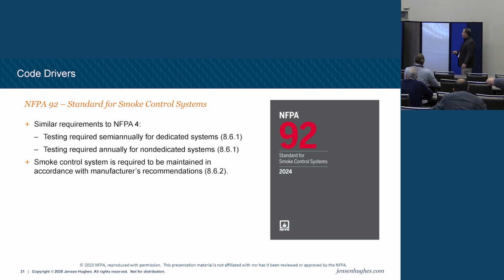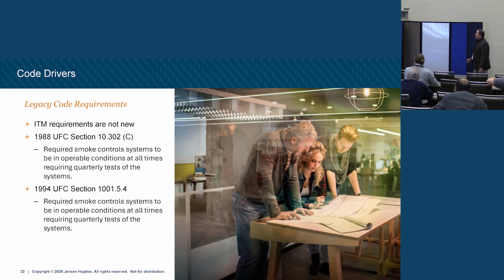Sounds the same. There's a correlating committee within NFPA that tries to make all the NFPA codes not contradict each other. It still happens, but it's very rare now. So this is one that's coordinated with NFPA 4. Okay, smoke control's not new. So if you're thinking, well, it's probably not in my building, it was built in 1989. Well, it was in the 1988 Uniform Fire Code. In '94 it was out there, and it goes back further than that. And the inspection, testing, and maintenance requirements go back even further. So you likely still have it in an older building.